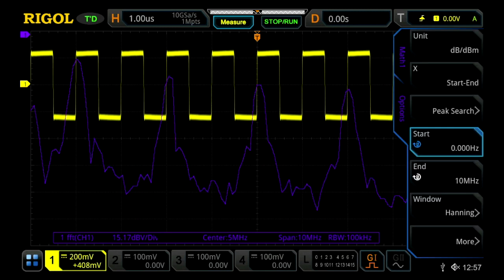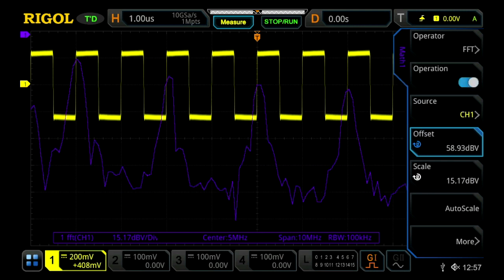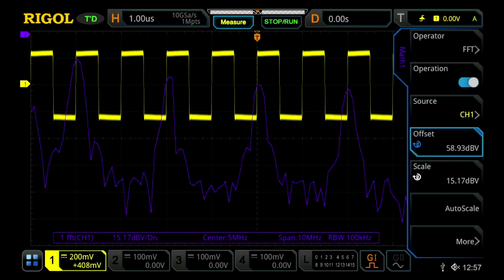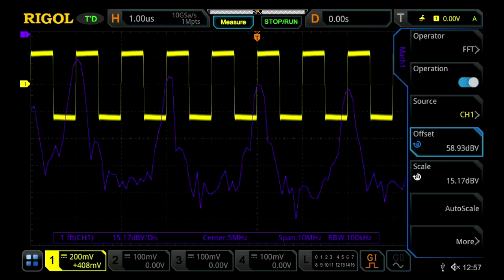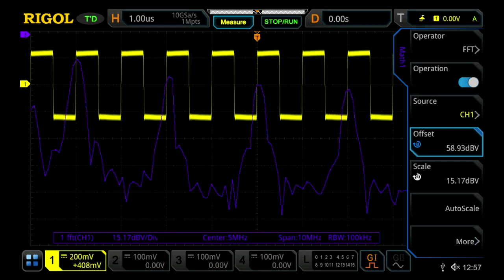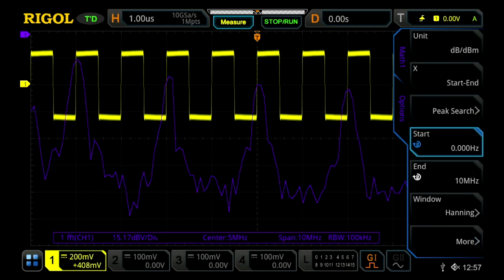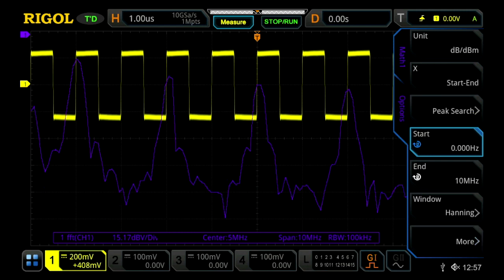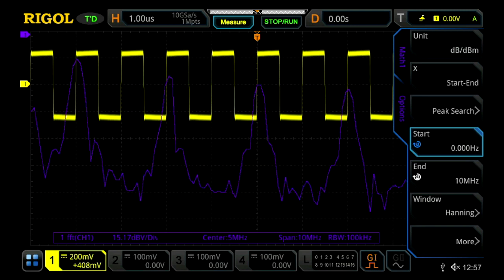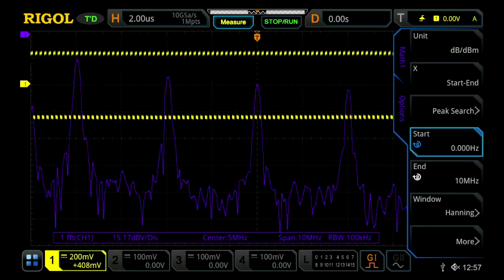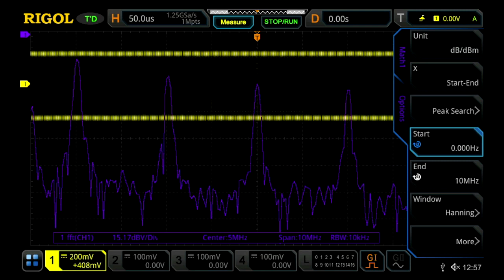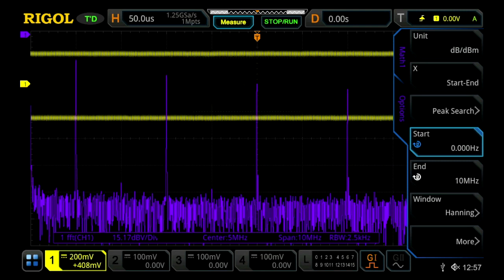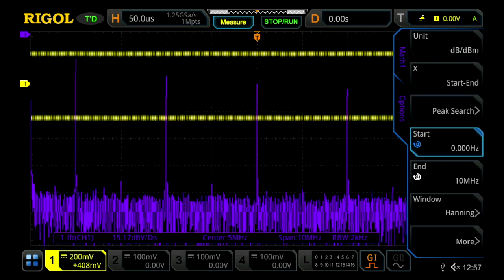Let's turn our menu back on. And within here, we can easily then change our offset and scaling if we wish. If we go into more, we're able to change our scaling, as I already showed you. Let's zoom this out a little bit by changing our horizontal display. We're changing our RBW setting down here in the bottom as we scale out a bit.